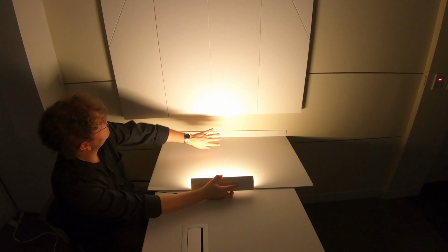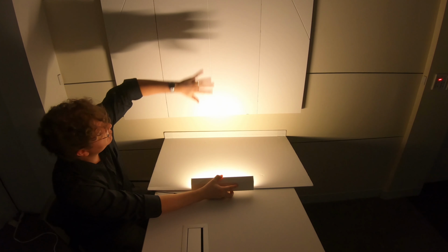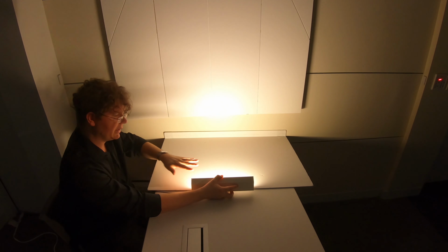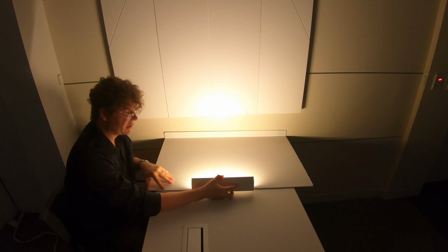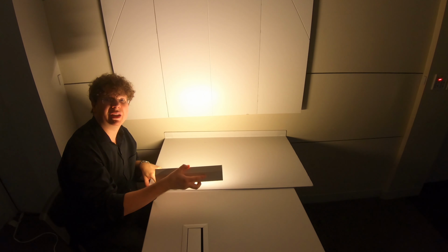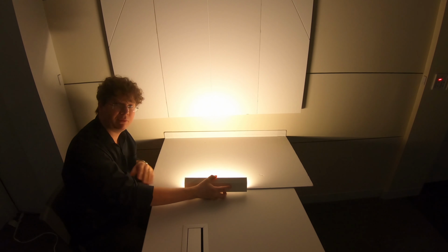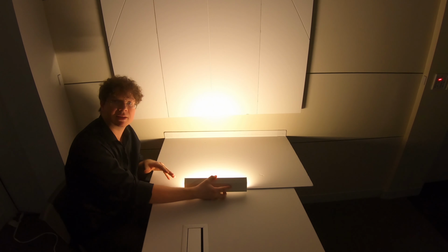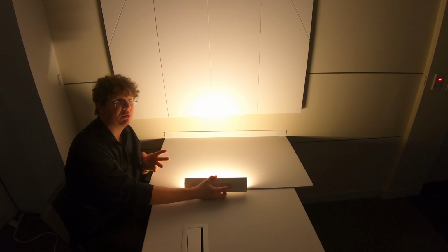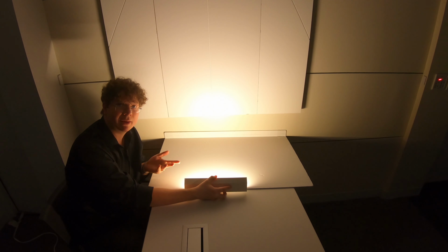It's providing uniform light and projecting a far distance up the wall, very even light across essentially the wall and the ceiling. These architectural fixtures can really simplify the lighting designer's part in the process because the optics of them are built into the fixture. You have to worry a lot less about cutoff and people being able to look into the luminaire.